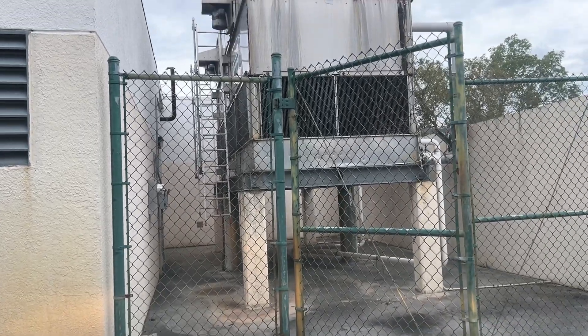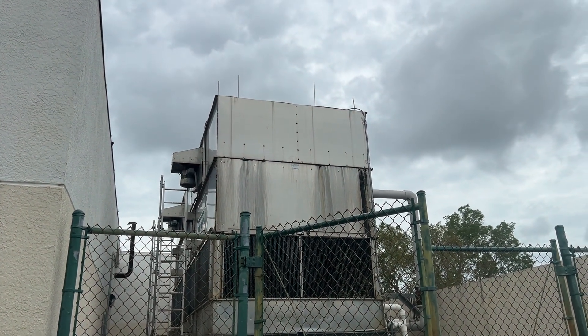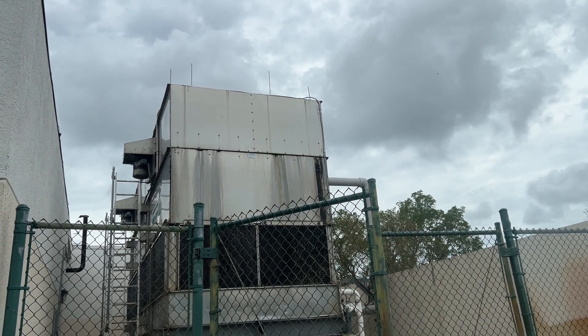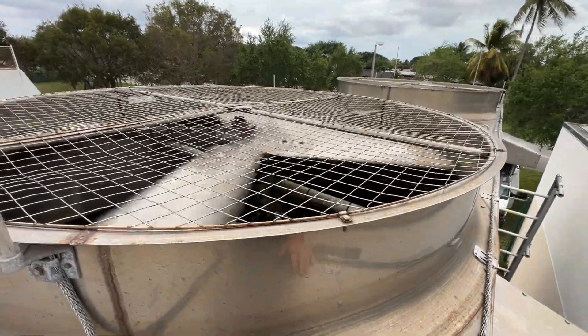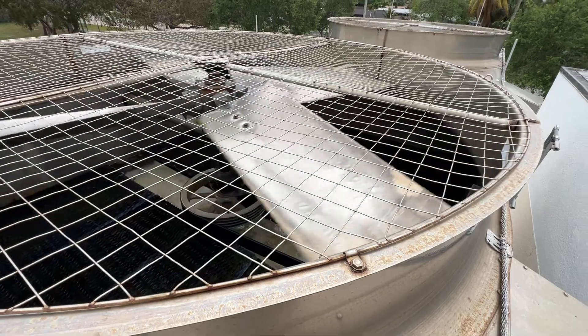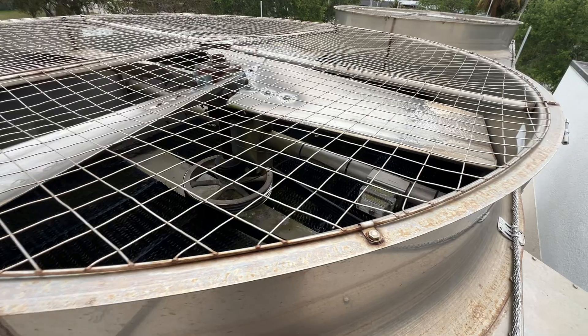While I'm waiting for an answer on those rails, I do have the belt for that tower right there, so we can at least change that out. We're not without chilled water — the other pump is working, it's leaking, but yeah. Let's change the belt. For those of you who asked about the blade going backwards on the one where I changed the belt — it was just some camera trickery, it's definitely going the right direction.